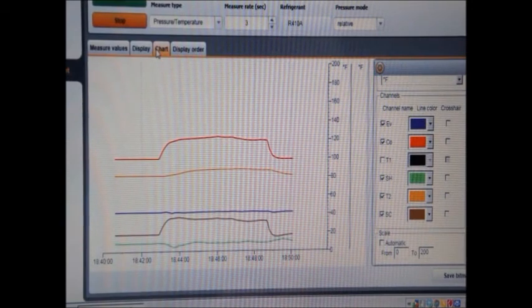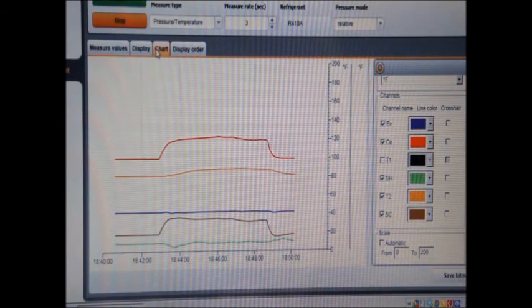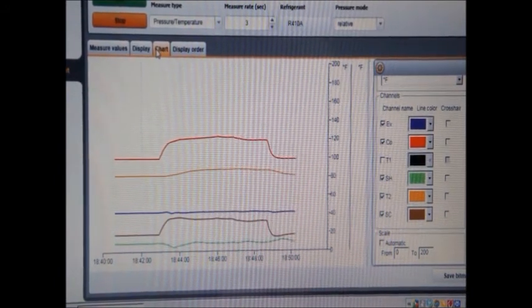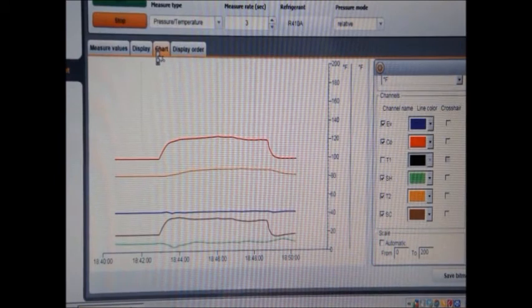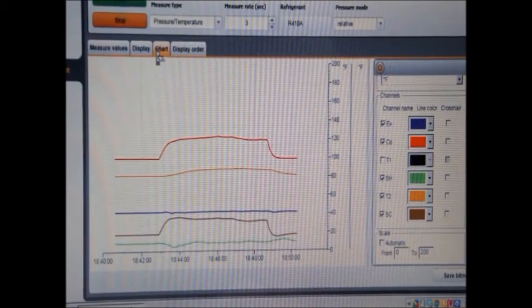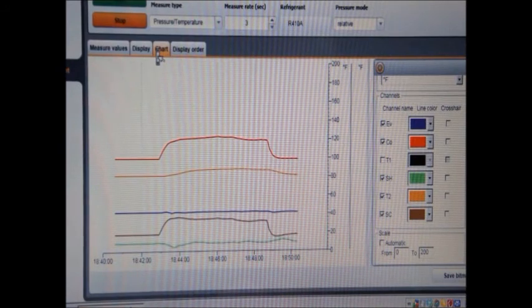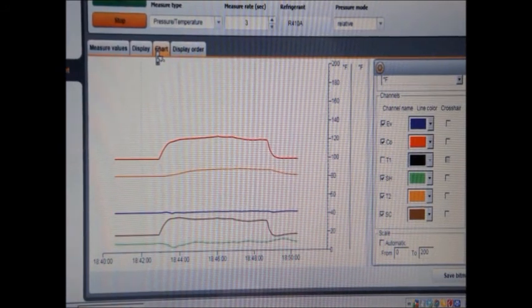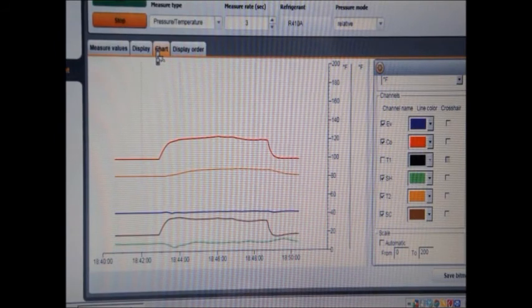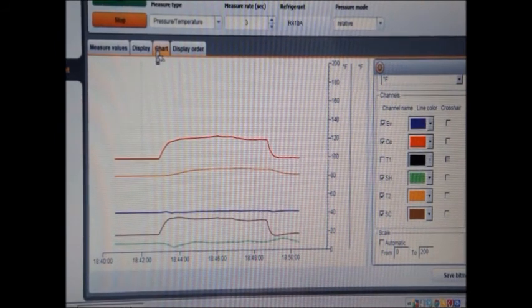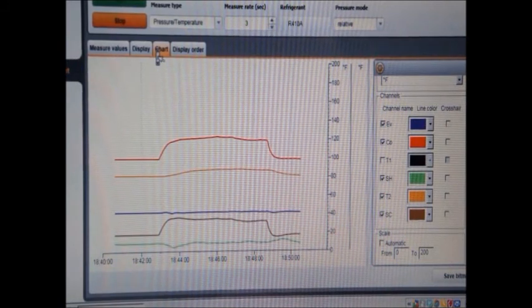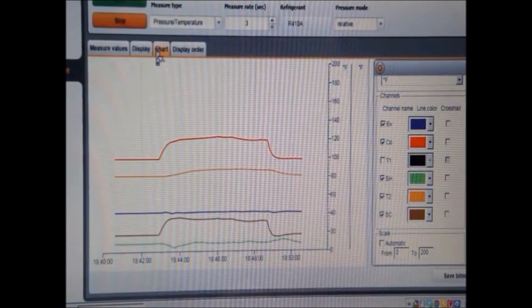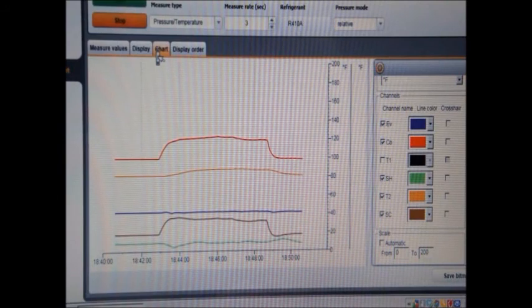Oversized condenser, increasing the pressure, which would also increase our wattage definitely because the compressor's working harder. We're going to see an increased compression ratio, increased electrical usage. Boy, if I were walking up to this the first time, I might have dumped some gas out of it not even knowing, thinking it was way overcharged. Even looking at the dirty condenser, because typically subcooling does not change with pressure. It's just, again, an oversized condenser.